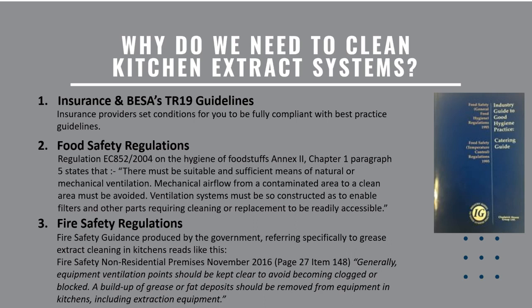However, not everyone knows or is aware that cleaning of grease extract is also covered by legislation. Food safety regulations, used significantly by environmental health departments within local authorities, provide guidance stating that ventilation systems must enable cleaning and be readily accessible. Fire safety guidance associated with fire safety legislation also refers to the importance of grease and fat deposits being removed from extraction equipment. But as I've said, there are significant challenges associated with this service.